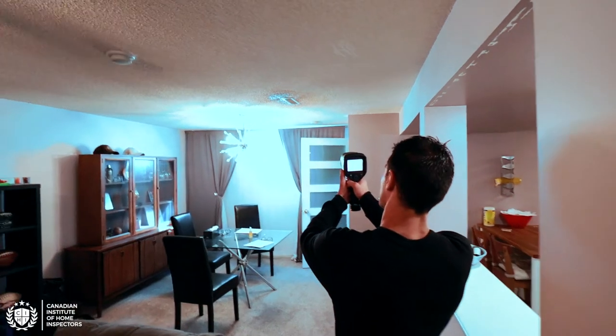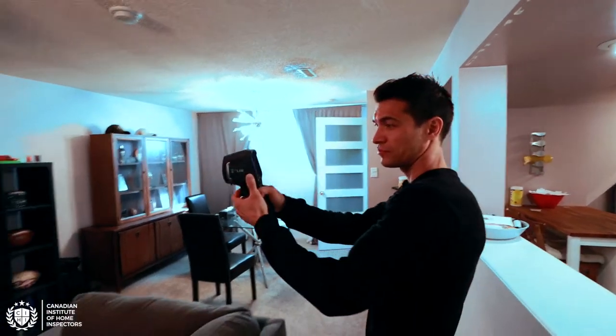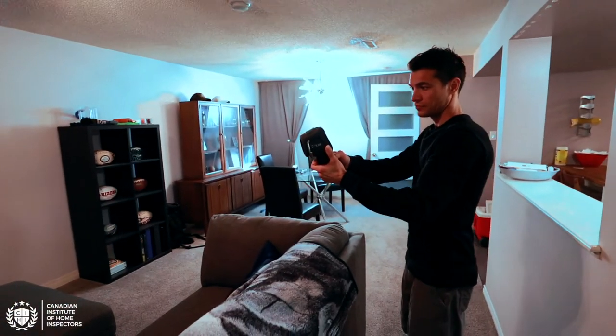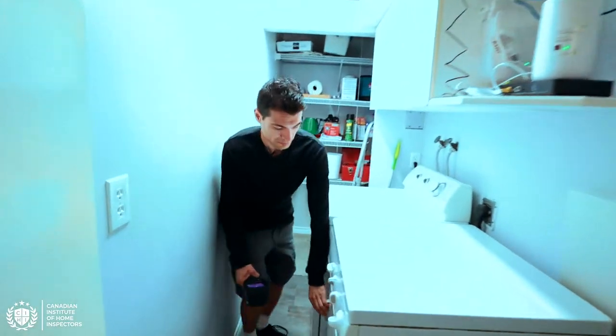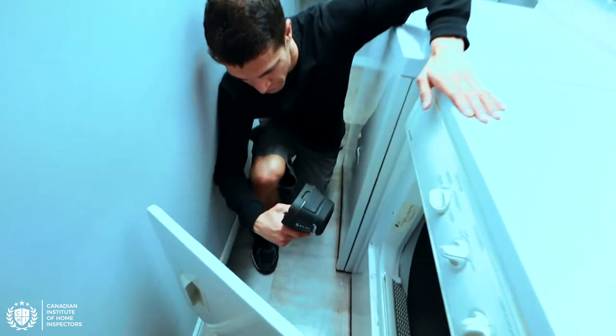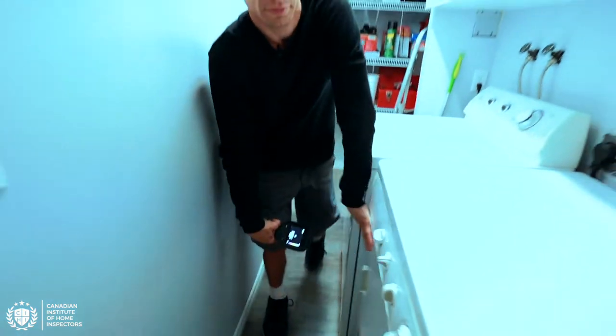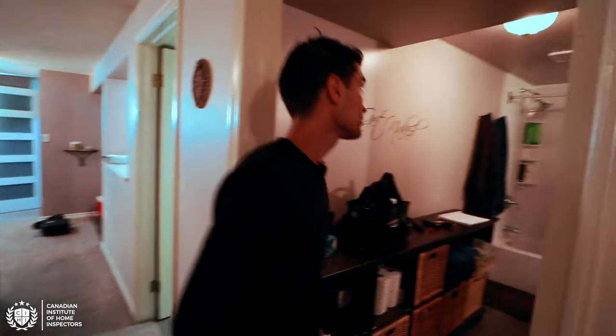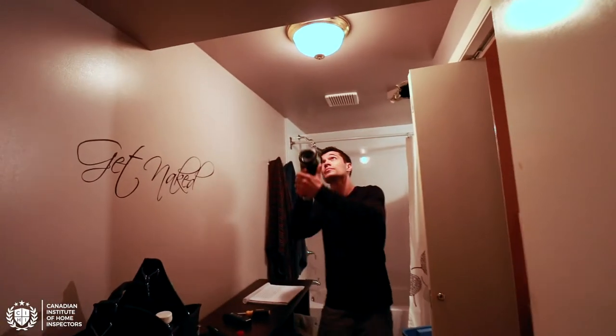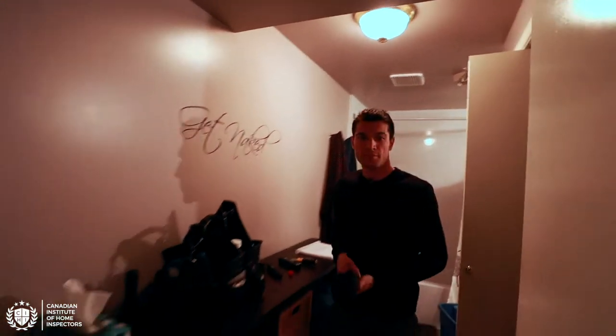After confirming there are no gas leaks, we want to verify the heating supply units such as the ducts and radiators are producing heat. Using a thermal imaging camera, temperature gun, or even your hand, go to each heating unit and confirm that it is operational. Oftentimes, you will find disconnected ducts or ducts that are covered by flooring and drywall. Naturally, you should include these deficiencies into your inspection report.